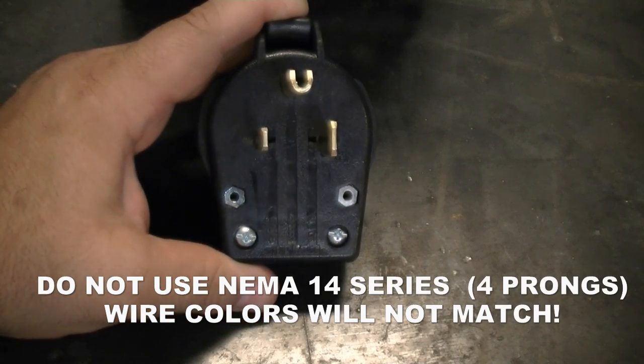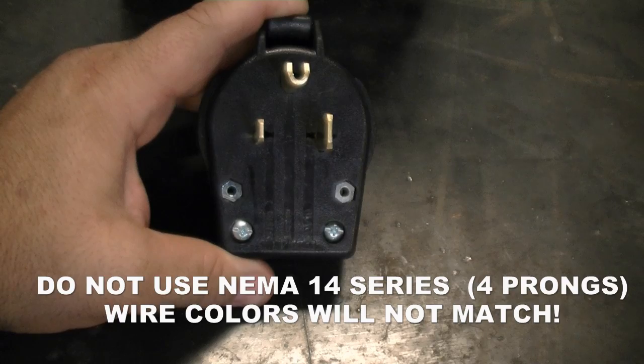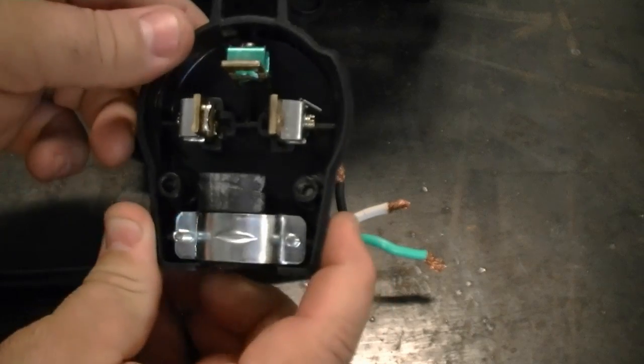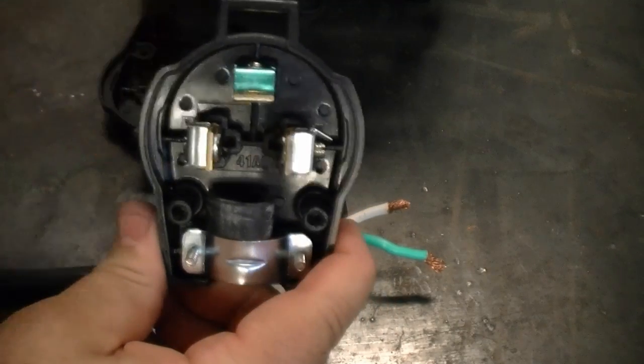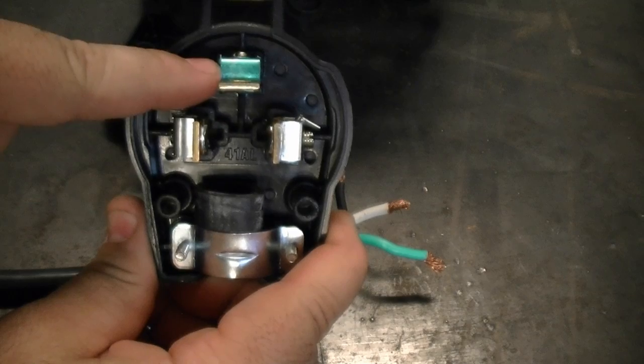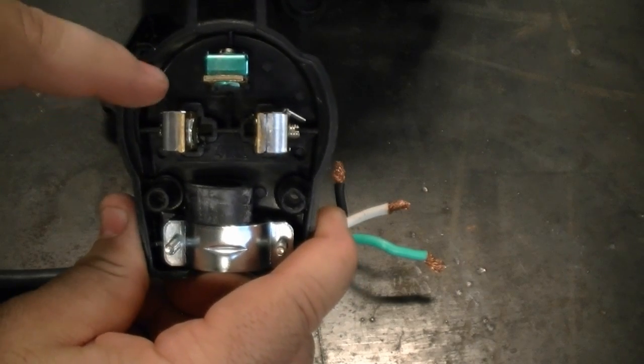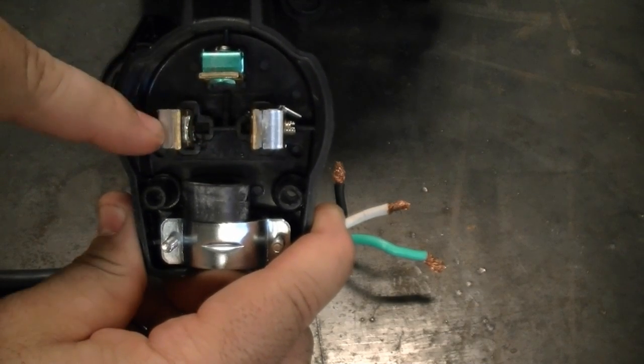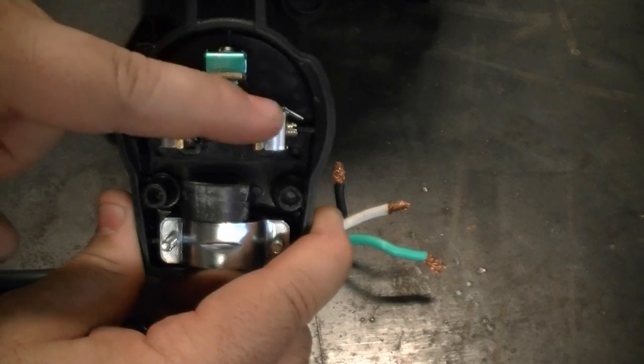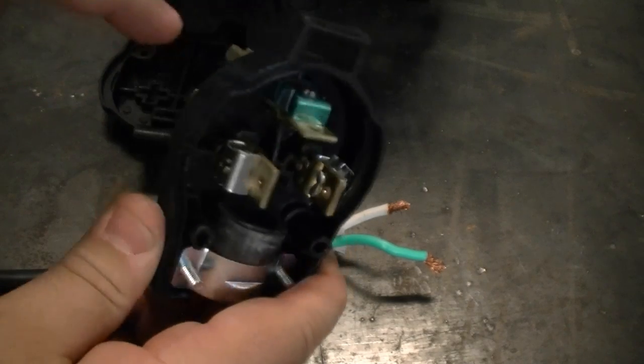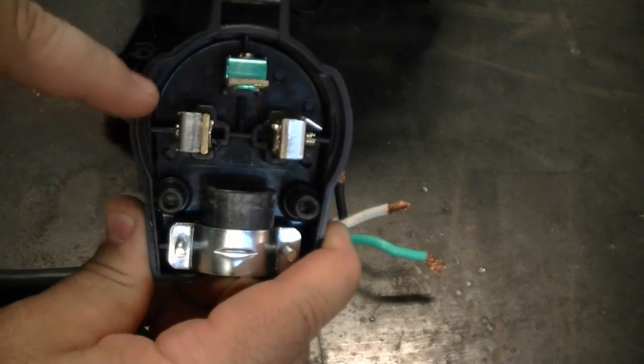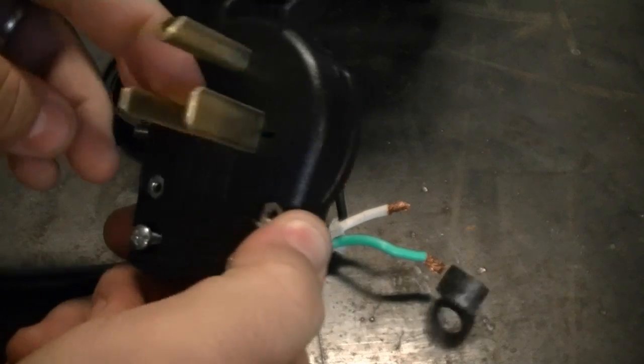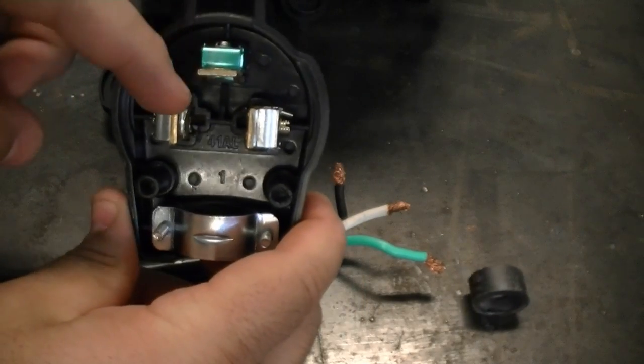Now the difference in this is that you don't have a red wire. Now if you open it up, it's also going to be fairly easy to understand. Here you have a green terminal, that's going to be your ground. In a 240 volt system, either leg is going to be hot, so it's really not going to matter except for local coding purposes which wire you use here, black or white or white or black. But typically codes require the black to be on the larger terminal, and the white to be on the smaller terminal. So keep that in mind when you're wiring.